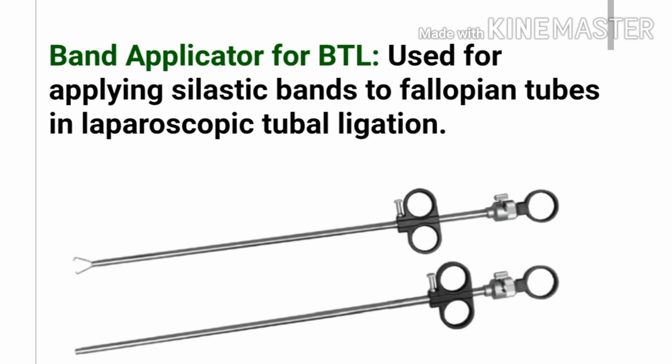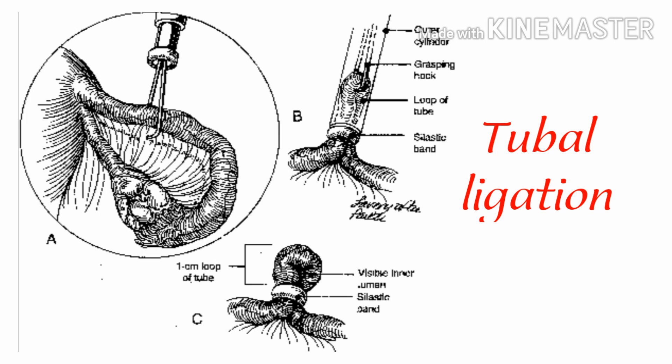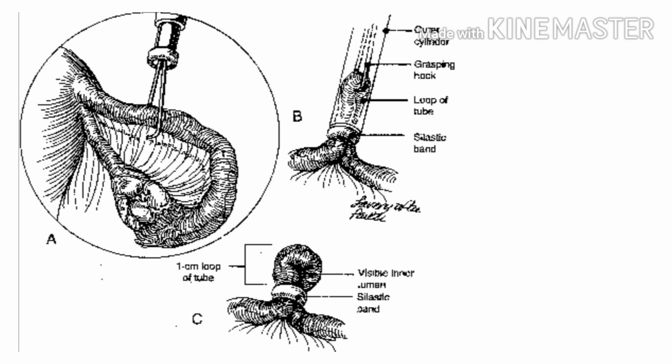This is the image of the band applicator. It is used for BTL — bilateral tubal ligation. It is used for applying silastic bands to fallopian tubes in laparoscopic tubal ligation. During tubal ligation, a two to three centimeter segment of the fallopian tube is drawn inside a narrow cone-shaped applicator. In figure A you can see how the band applicator holds the fallopian tube, in figure B the loop of tube with the grasping hook and silastic band, and in figure C the one centimeter loop of tube with the silastic band.